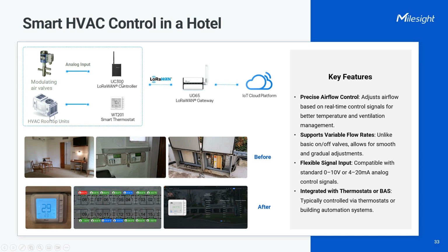Next, 16 UC300 controllers were installed, one per room, to control the existing modulating air valves according to the command from the management system. These valves receive analog signals, typically 0 to 10 volts or 4 to 20 milliamps, allowing for precise variable airflow rather than basic on and off control. This ensures smoother temperature regulation and better energy efficiency.